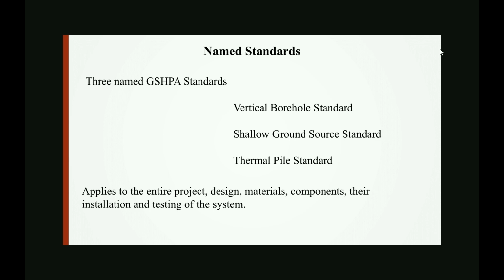Now, three of those standards were written by the Ground Source Heat Pump Association. That's their vertical borehole standard, the shallow ground source standard for horizontal systems, and also the thermal pile standard, which is used in construction. Those standards apply to the entire project: the design, the materials you use, any components, how you install them, and also how you test the system. And I'm going to be dealing now with how we actually test the loops.